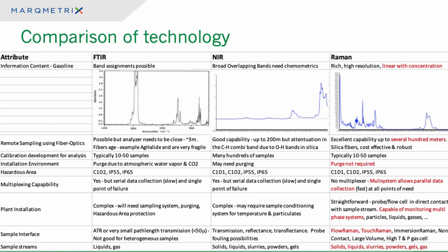On the installation side, one of the key differentiators with Raman and the way we do Raman with some of our ball probe technology is we have the ability to effectively place probes directly in the process, high pressure, high temperature, high flow, and we're capable of monitoring multi-phase systems. We're not specific to particulates or liquids. We can do mixed systems. And our sample interfaces we'll touch on more today. Some of our flow Raman technology, our touch Raman technology, as well as some of our other probe tech. And sample streams, as I mentioned earlier, we can cover the full range from solids, liquids, slurries, powders, gels, and gases. We can do most all of those with the same exact sampling optic. It's not like we have to have a suite of probes to allow us to do the different things. We can do most all of them with a single probe.